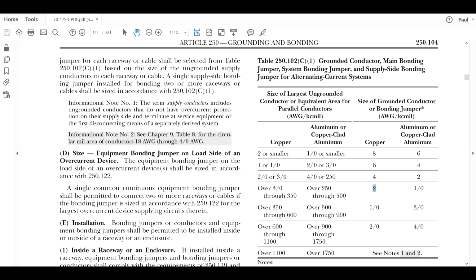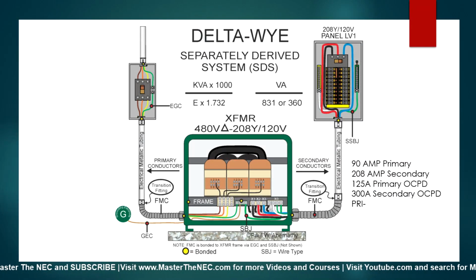Okay, so when we go back to the presentation, this conductor right here, the supply side bonding jumper, is going to be size 2 gauge. Now remember, these were 350s, the derived conductors, and this right here is a 2 gauge. So there you go. That's your supply side bonding jumper requirement.